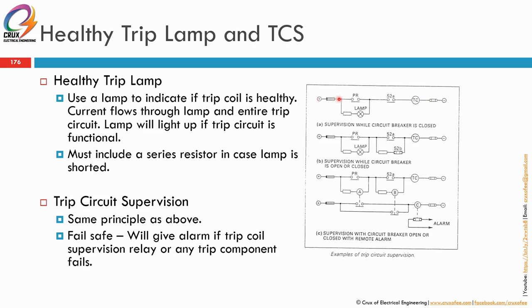So under normal condition, the protection relay is not triggered. There is a small current flowing through here when the breaker is closed, so this circuit is monitoring in the closed position. 52A is the normally open contact of the breaker. 52B is the normally closed contact of the breaker. So when the breaker is closed, 52A will become true and this contact closes. So this protection relay is only waiting for the protection to be triggered.